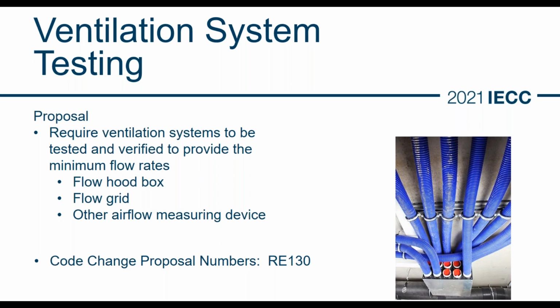So one of the big questions though is you can install your ceiling fans and your exhaust fans, for example, in bathrooms, but do you actually get the CFM out of those fans that you think you're getting after they're installed? Because the fan might be rated at a certain CFM, but once it's connected to the duct that leads to the outside, you may not actually get the CFM out of that fan that you think you're getting because of the duct run. So this would actually require you to test to make sure you're getting the right amount of CFM from a ventilation system.